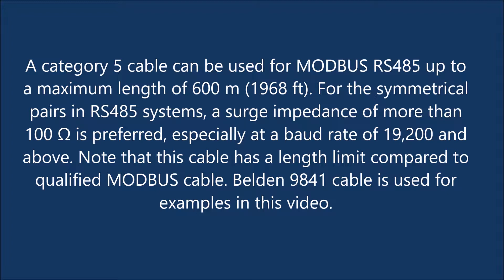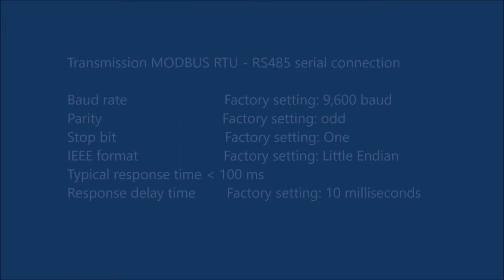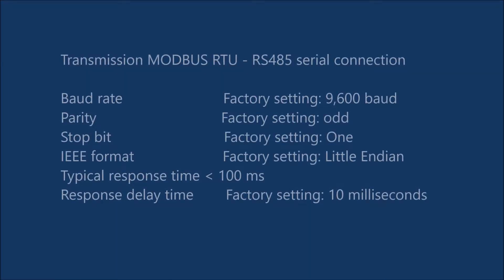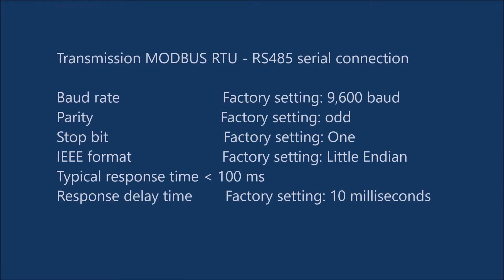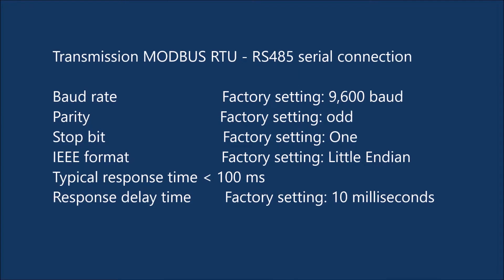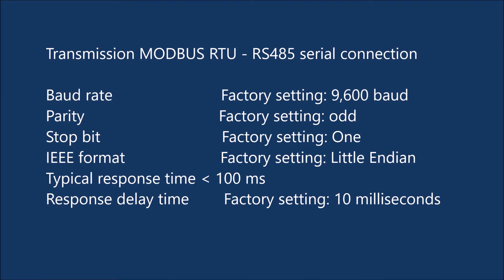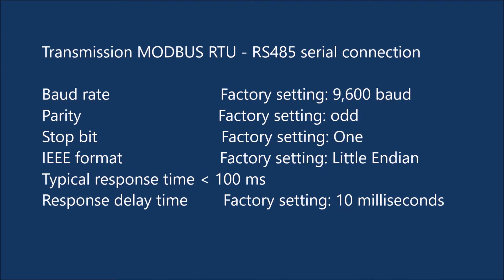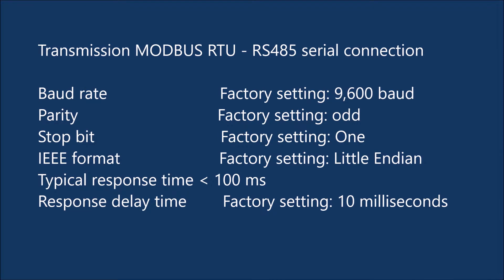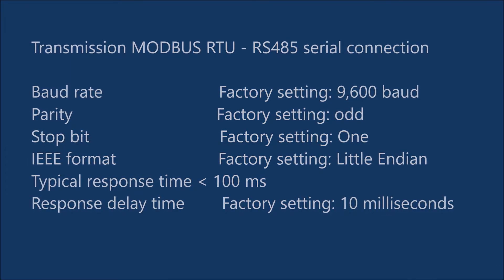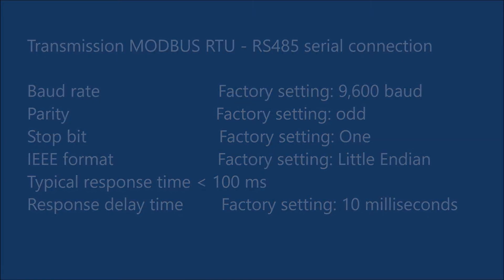Belden 9841 cable is used for examples in this video. Transmission: Modbus RTU RS-485 serial connection. Factory settings: baud rate 9,600 baud; parity — odd; stop bit — 1; IEEE format — little endian. Typical response time is less than 100 milliseconds. Response delay time factory setting: 10 milliseconds.